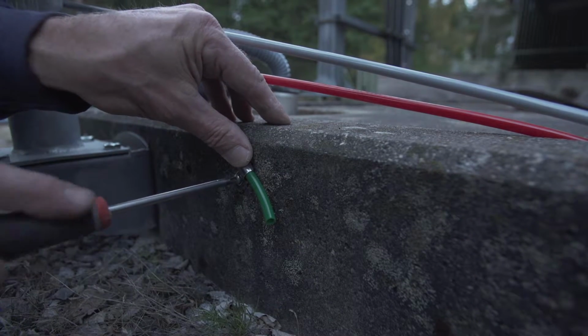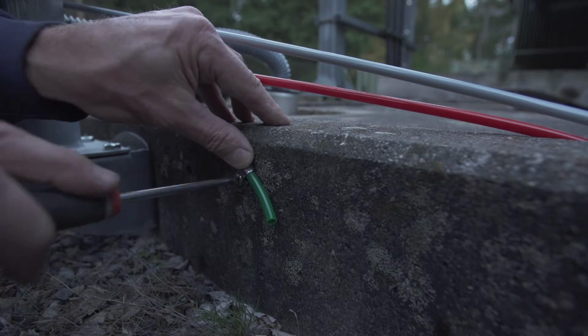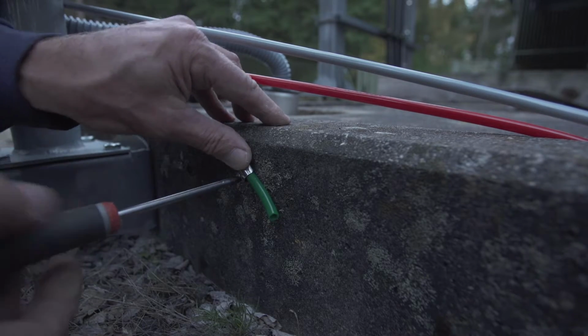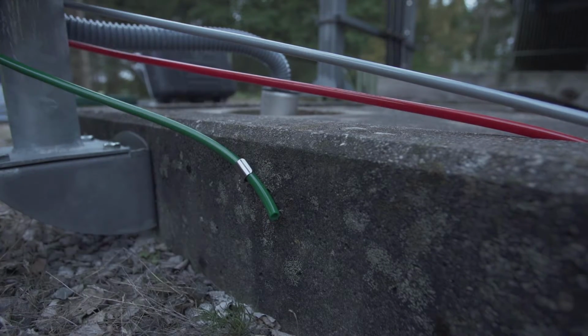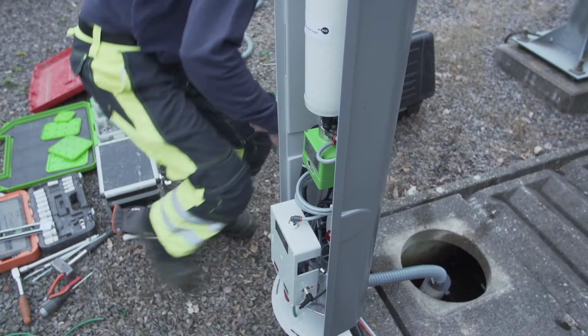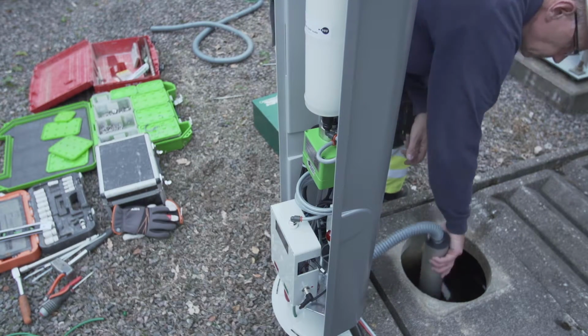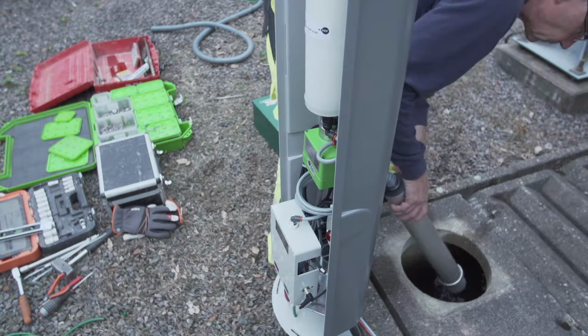The outlet hose must not be longer than 5 meters, and if the outlet needs to be longer, extend using a 12 mm transparent hose. Consider possible burial of drainage pipes or the possibility to lead the outlet to a draining well.